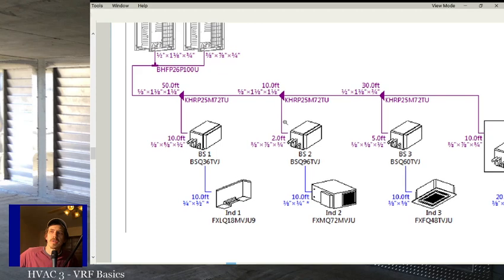And that is so that you can calculate the size of the line set, because how many tons is connected to it, which is one of the most important factors, dictates the size of your line set. So the more tons connected to that line set at a particular point, the bigger it's got to be, right? The longer the line set is, the bigger it's got to be. And if you get too far, you may have a problem. You may get primarily an oil return problem, right? Or too much pressure loss if it's not sized big enough. But if you size it too big, you'll get oil return problems.